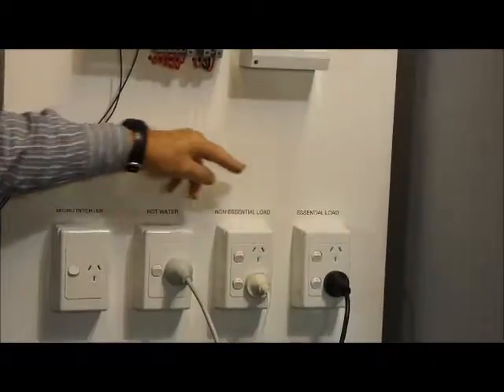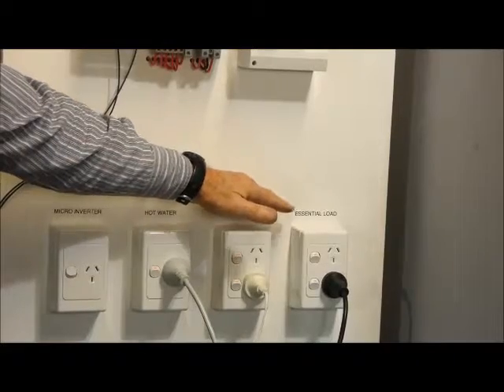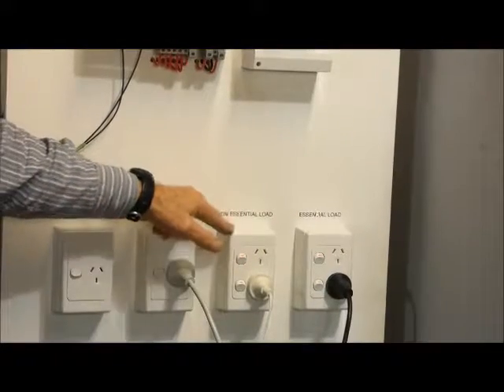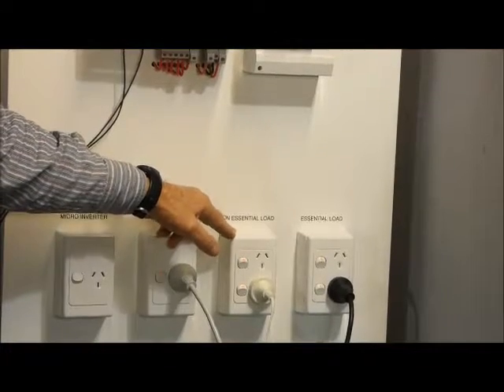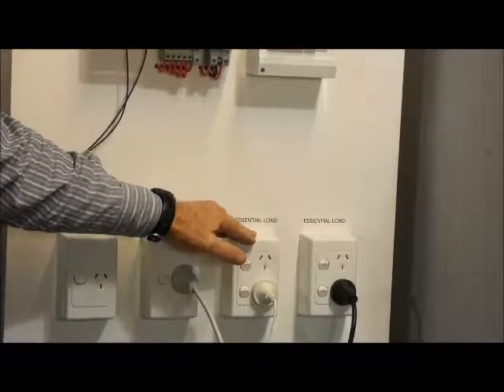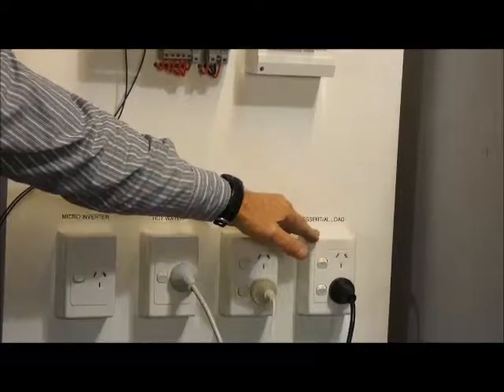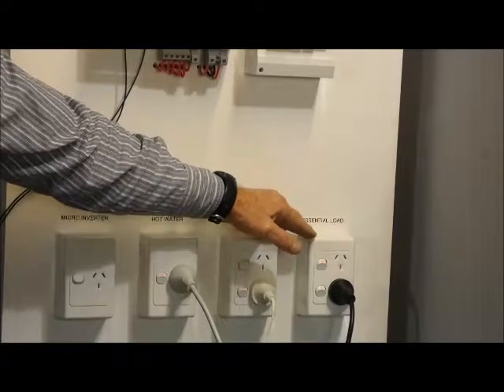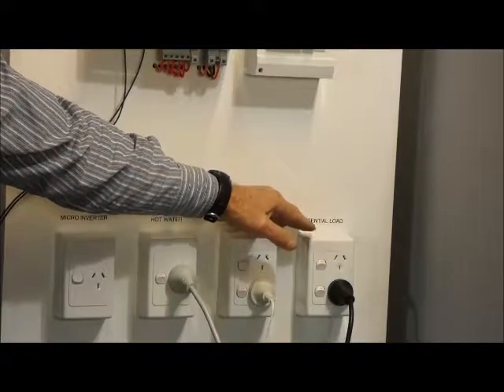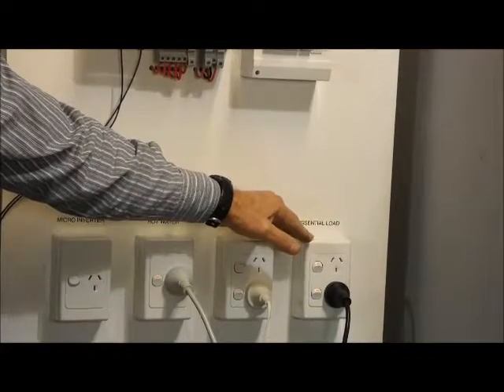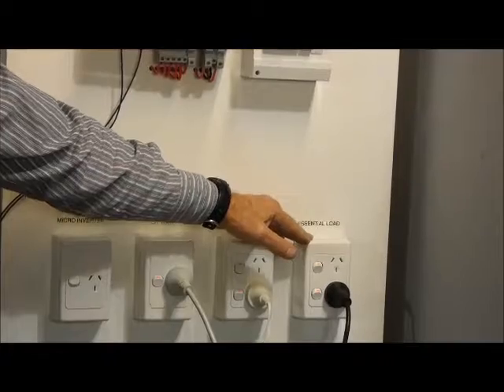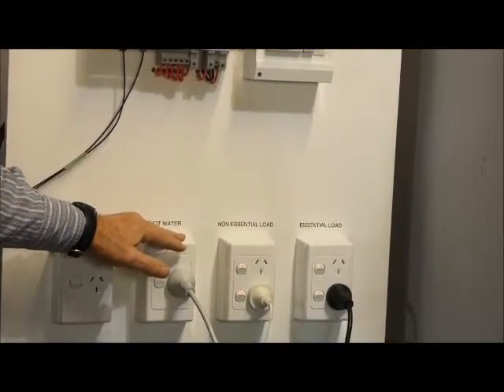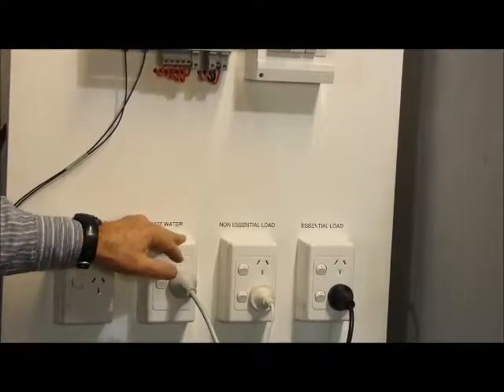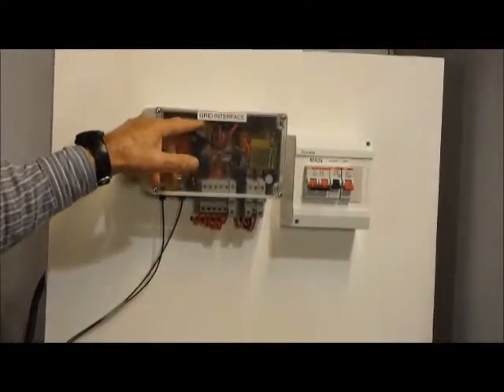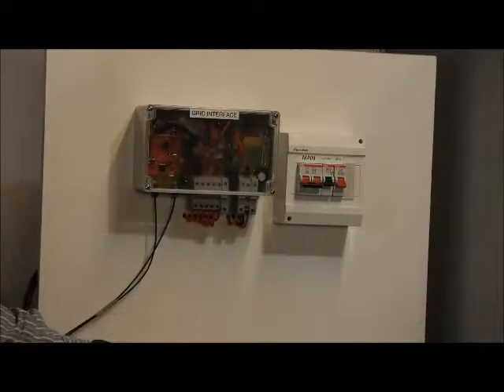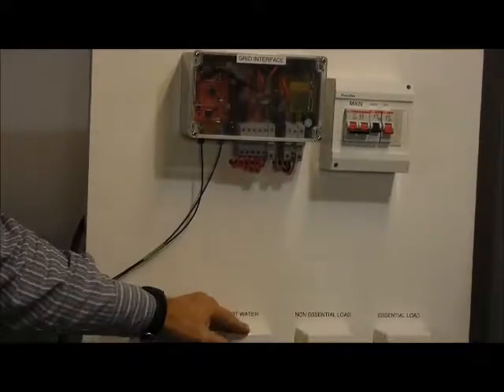Down here we have various circuits which would normally be in a house. We have a non-essential load circuit which is directly connected to the grid. This one's not backed up when the house goes to standalone mode. We have an essential load circuit which is directly powered by the inverter whenever the house is being run standalone from the inverter and not connected to the grid. We have a circuit standing in for the electric hot water heater, and also in here we have a relay that can turn that on and off. So if you're running standalone, that would normally be only turned on when the batteries were fully charged.